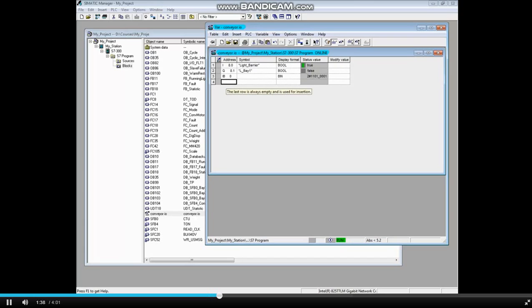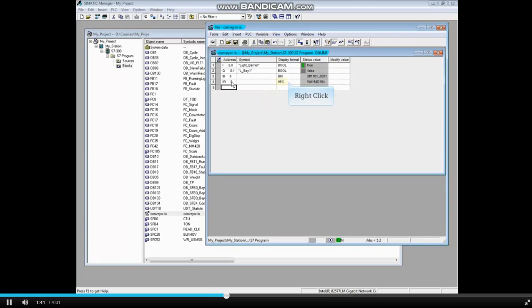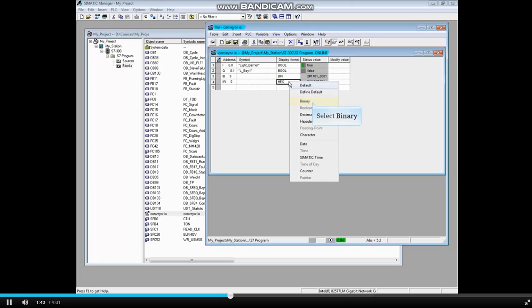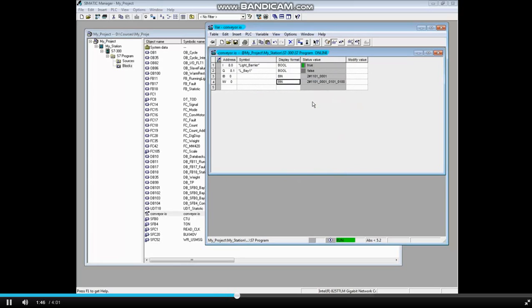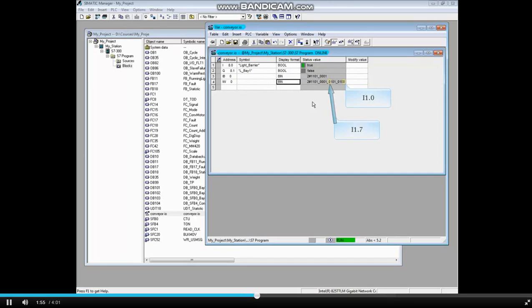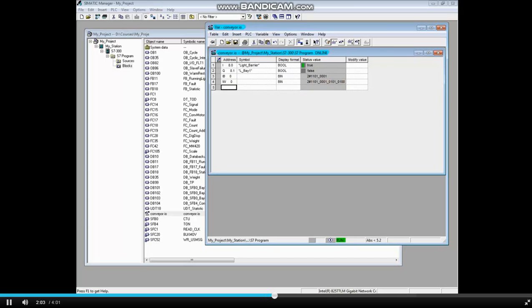Now let's monitor input word 0. Change this to binary as well. Here are the bits of input word 0. Byte 1 is on the right with the right most bit being input 1.0. The eighth bit from the right is input 1.7, then is input 0.0, and the farthest left bit is input 0.7.